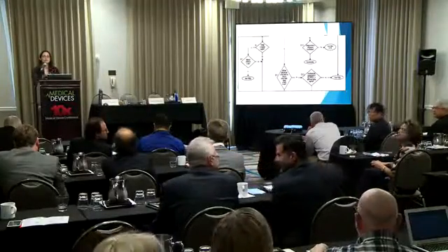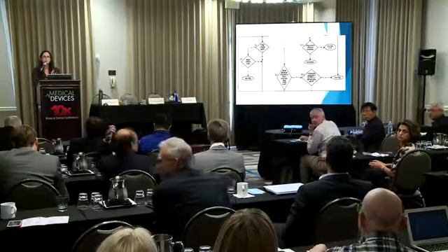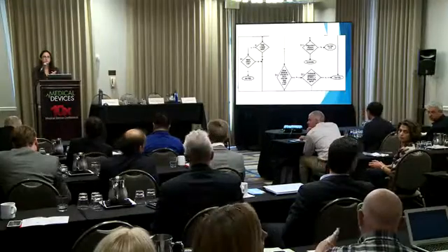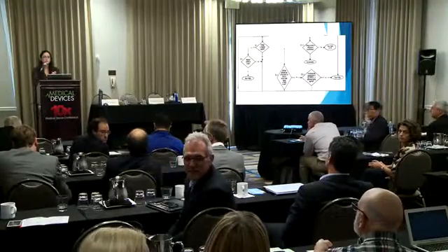Just a comment. I heard a lot of questions about 510K and now de novo. There is a pre-submission program FDA has. Great program. If you have a straightforward 510K, you know exactly what you're doing, go for it. But if you're taking multiple devices or multiple product codes and you're not sure if you need a clinical study or not, even class 2 devices now they're asking for a clinical study, I would suggest going for pre-submission.